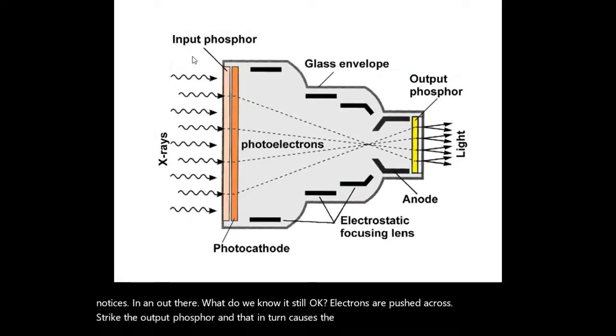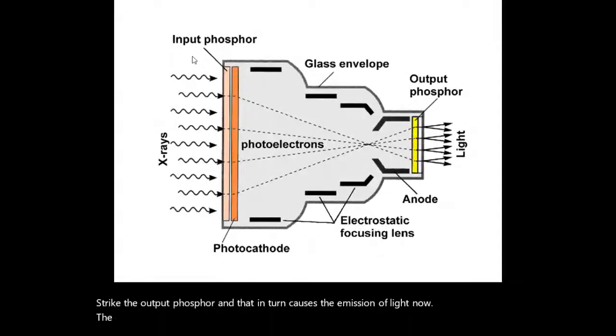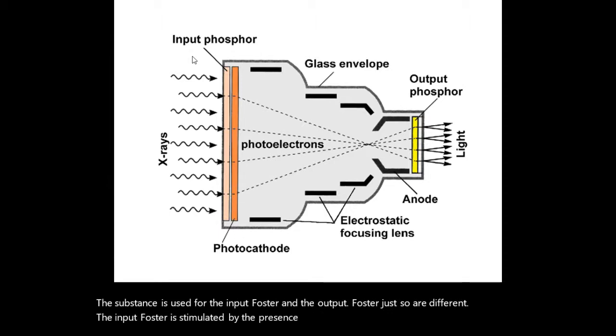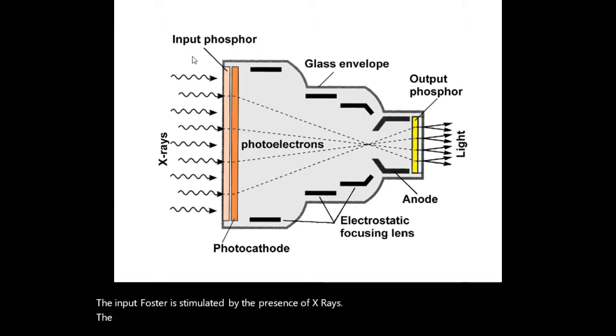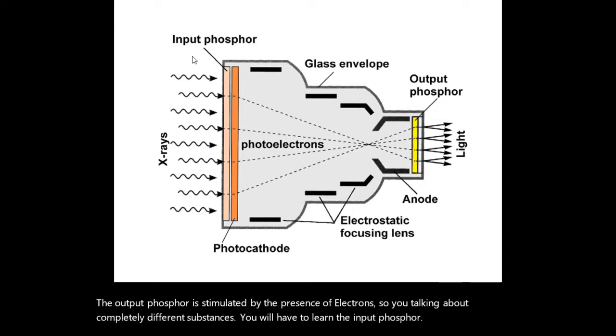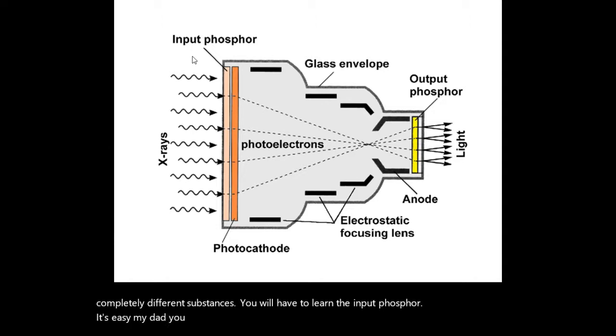emission of light. Now, the substances used for the input phosphor and the output phosphor, just so you know, are different. Okay, the input phosphor is stimulated by the presence of X-rays. The output phosphor is stimulated by the presence of electrons. So you're talking about completely different substances. You will have to learn the input phosphor, that's cesium iodide. You don't have to worry about the output phosphor.